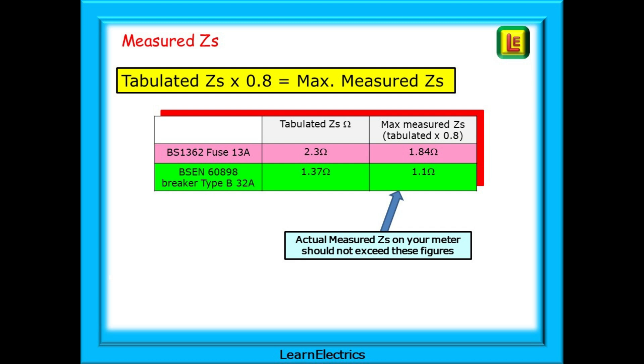For the 13 amp BS 1362 fuse, 2.3 multiplied by 0.8 is 1.84 ohms, and this tells us that our measured reading with our test meter should not exceed this 1.84 ohms in value. For a type B 32 amp BS EN 60898 circuit breaker or RCBO, 1.37 ohms multiplied by 0.8 is 1.1 ohms. Part of the circuit protected by this device should not exceed a measured value of 1.1 ohms.